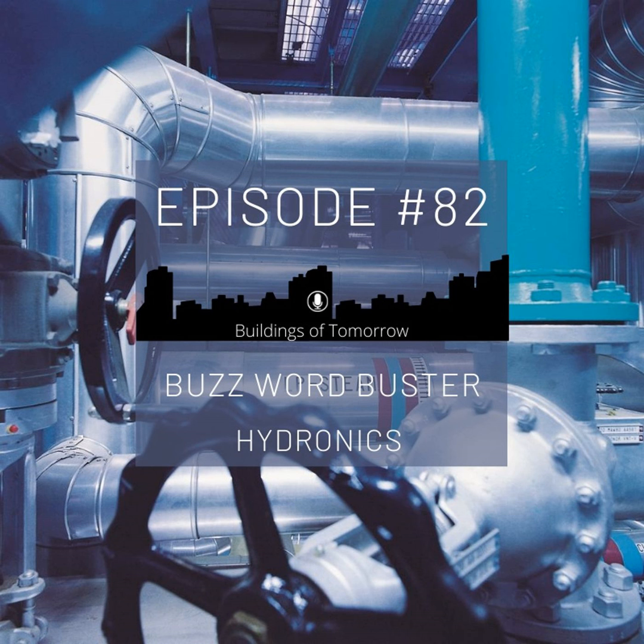And delta P constant means just that it maintains the pressure, or the pump head, as we say it, that the pump brings at design. It maintains always this amount of pressure. It doesn't go above, but it also doesn't go below. It says, for example, we have 7 meters of water column that we need as pump head at design, and the pump always maintains that amount of pressure, whether it's needed or not. And in order to maintain that at lower volume flows, it will reduce the speed somewhat, a little bit.